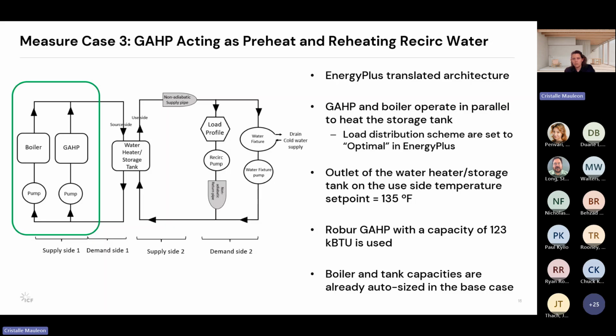The GHP used in this model has a capacity of 123 kBTU per hour, and the boiler and storage tank capacities were auto-sized in the baseline, and they were reused here. This architecture allows the GHP to preheat the mixed recirculation and city water. Modeling this setup in Energy Plus required some simplification. Heat exchangers between the GAHP and the potable water were omitted to avoid overriding flow dynamics in Energy Plus because it can't balance them across parallel branches, as I mentioned earlier.